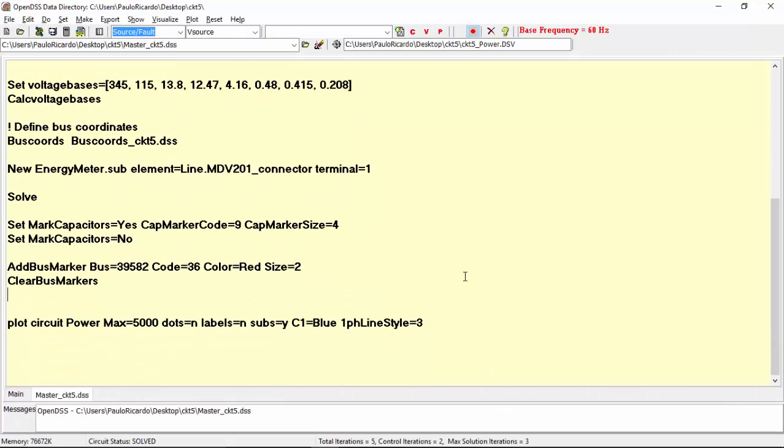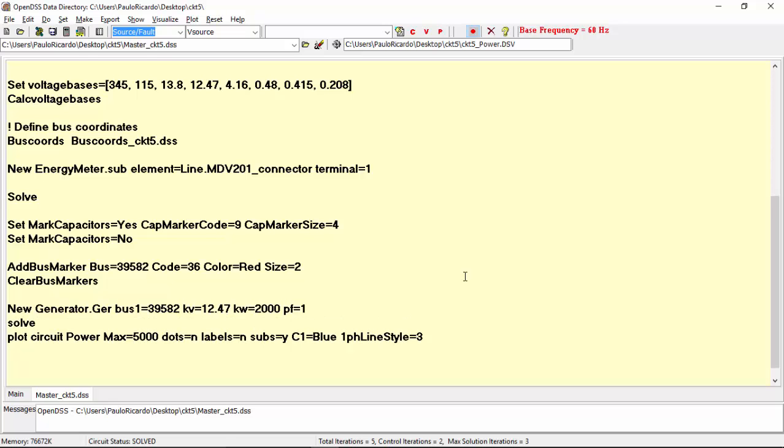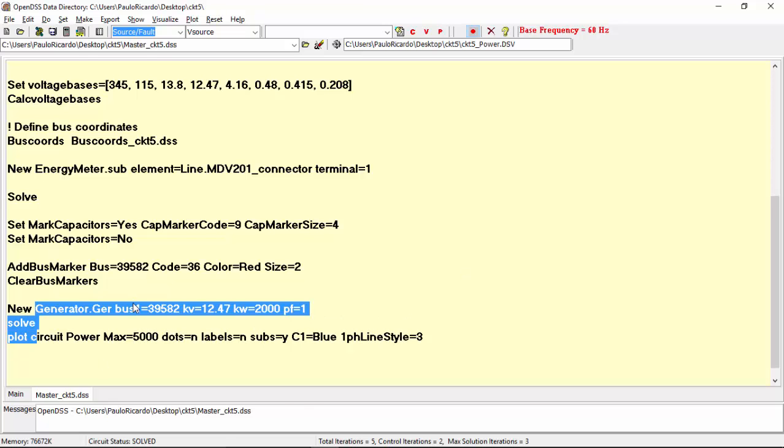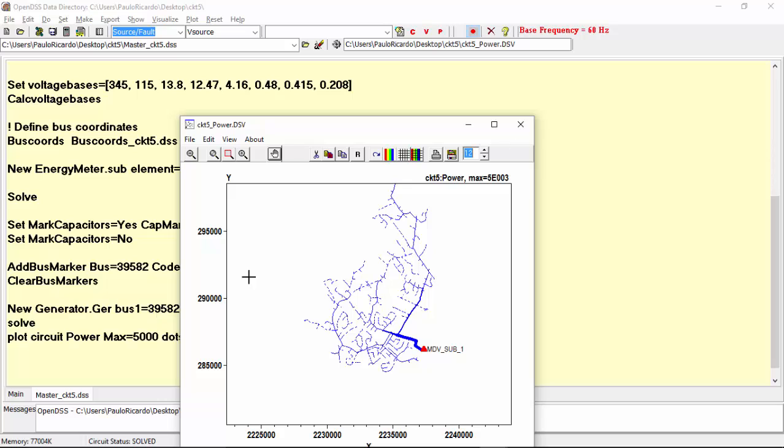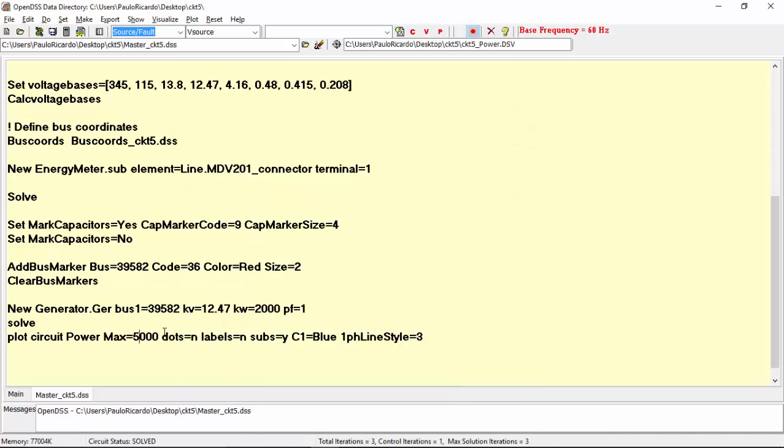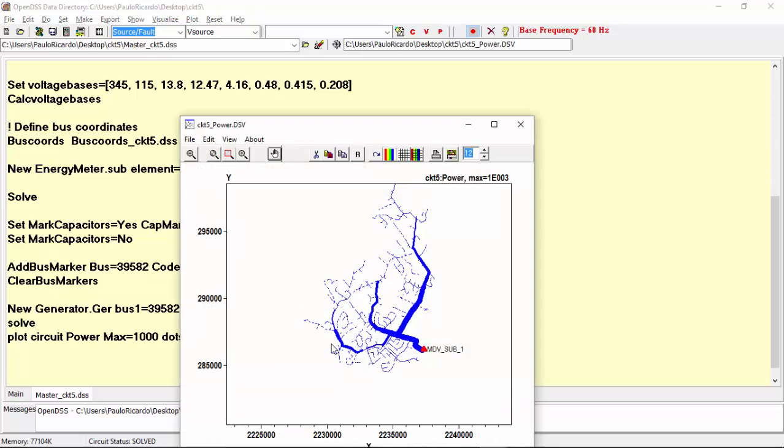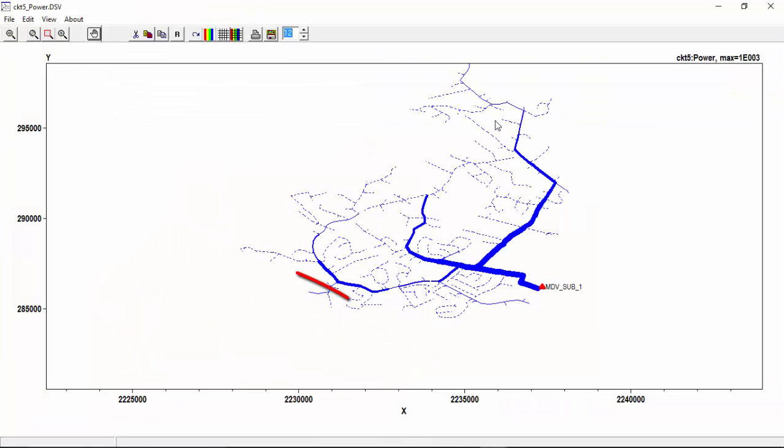Now, assume, for example, a generator connected to the same bus with an injected power of 2000 kW. Solving the circuit, it is difficult to see the impact of the generator with the power flow represented by the thickness of the lines. Again, this is due to the fact that the maximum scale is not adequate for that. You have to adjust it according to the power generator. For example, let's set it to 1000 kW. Now we can see that a great amount of this power is flowing upstream.